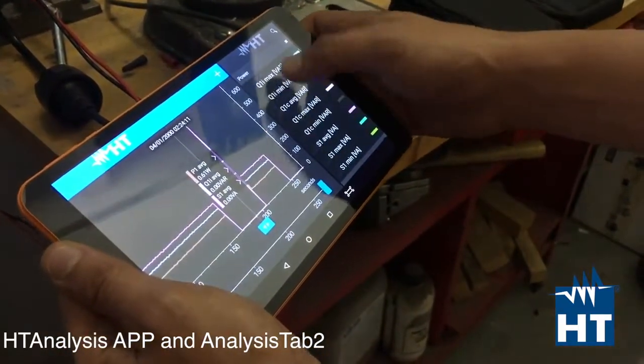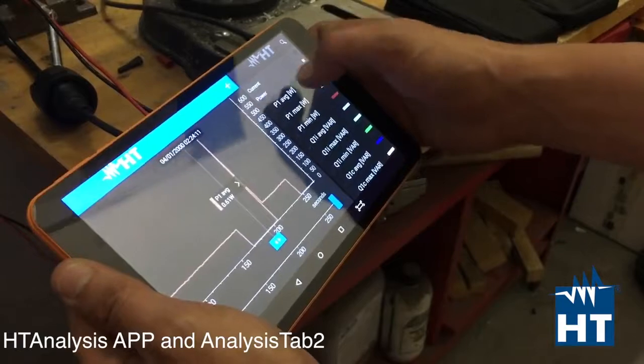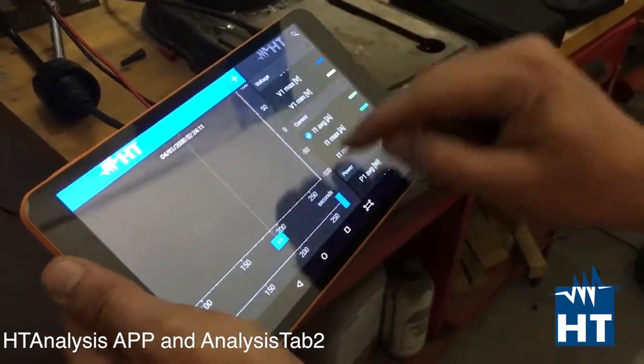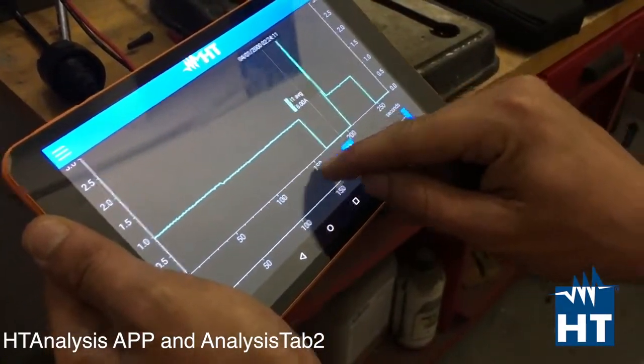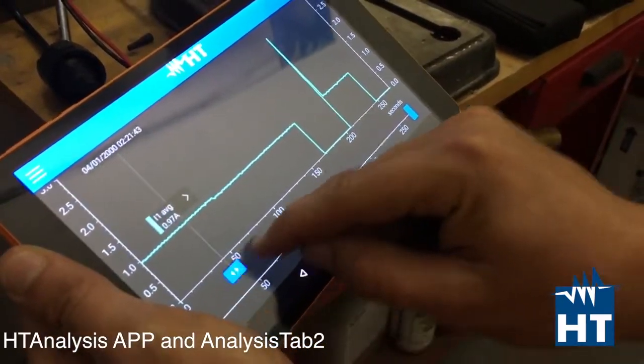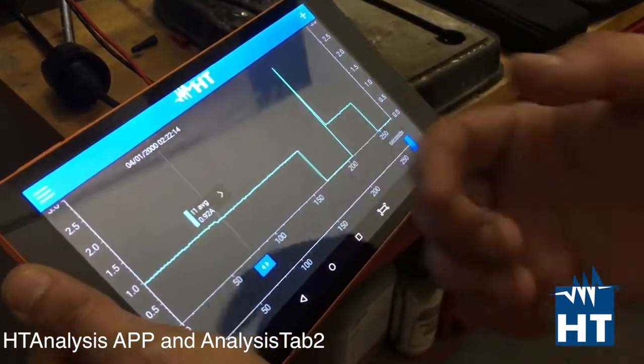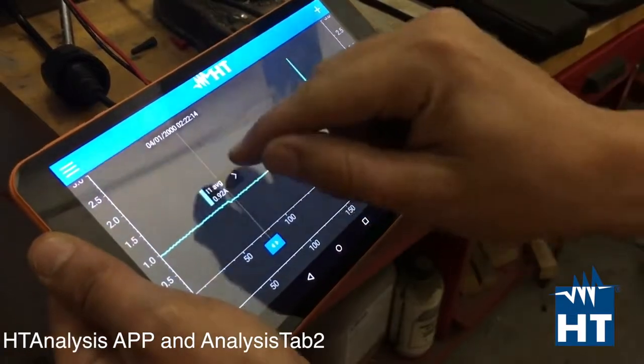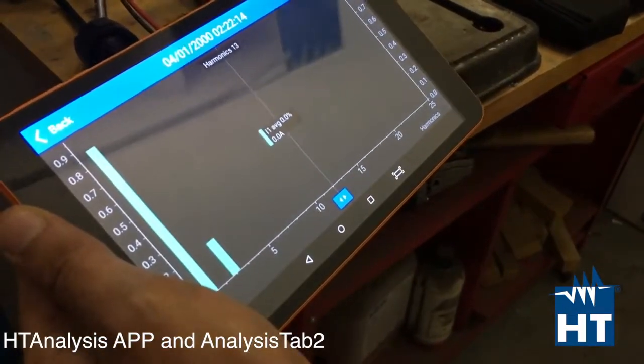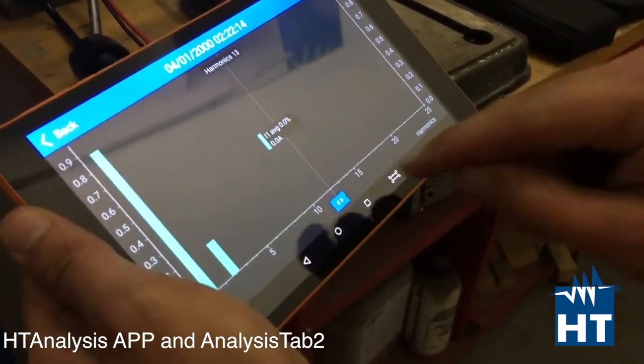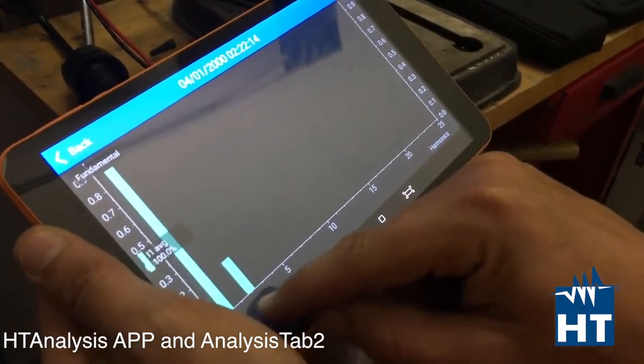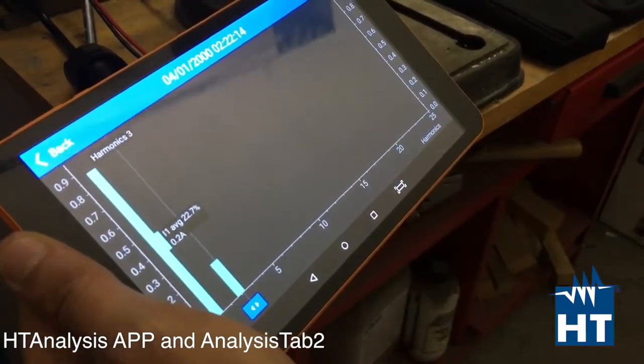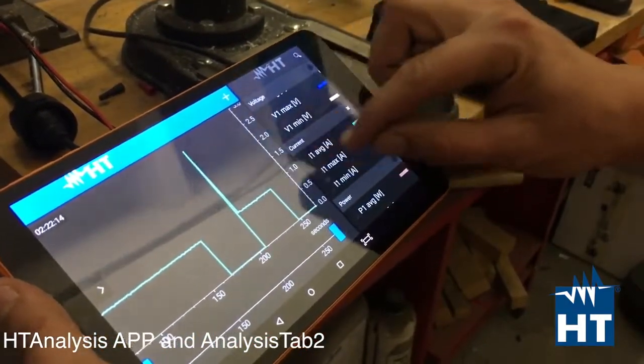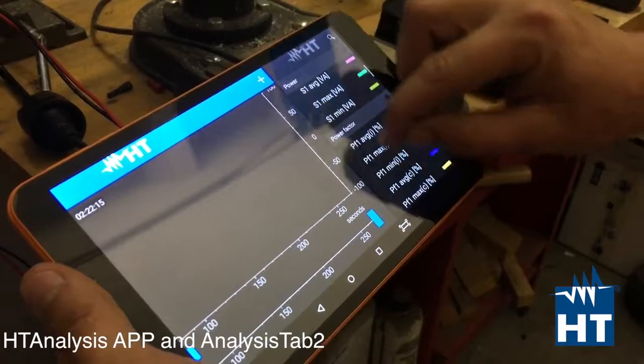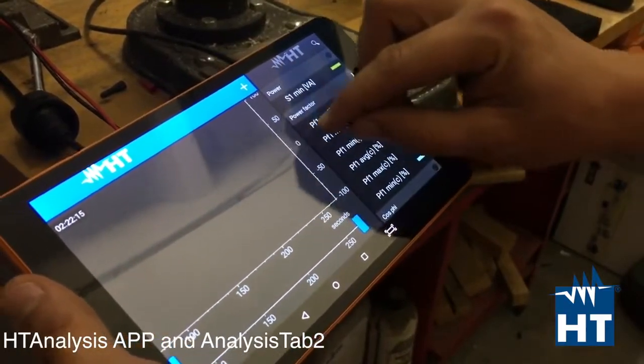More accurately, you can remove the power. Take a look again at the current, for example. Here we have the current graphs. We can switch the value at different points. Then again with the jump function, by clicking on the current button, you will jump to harmonics. So here we have the harmonics of current in that specific period of time. We can do a lot of things more. We can even see the power factor, for example.